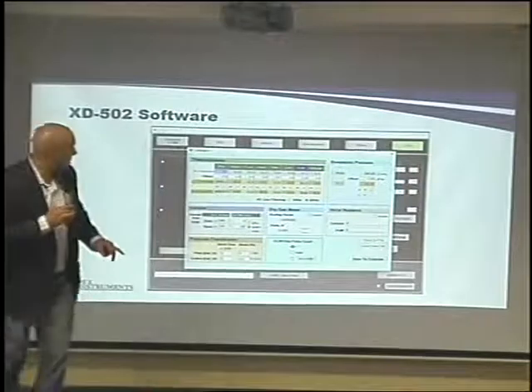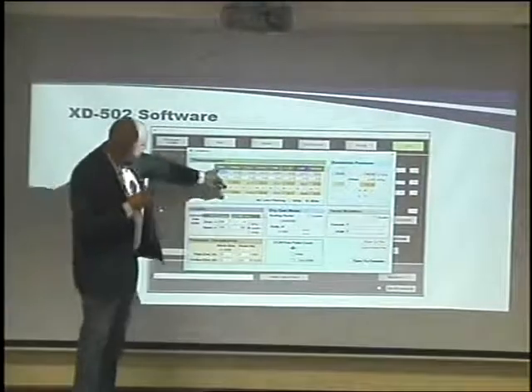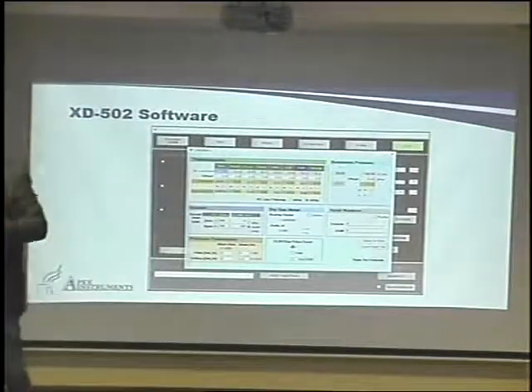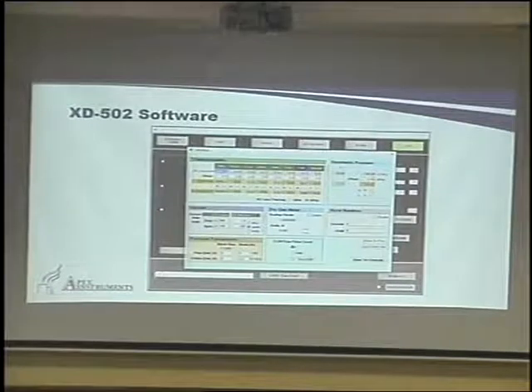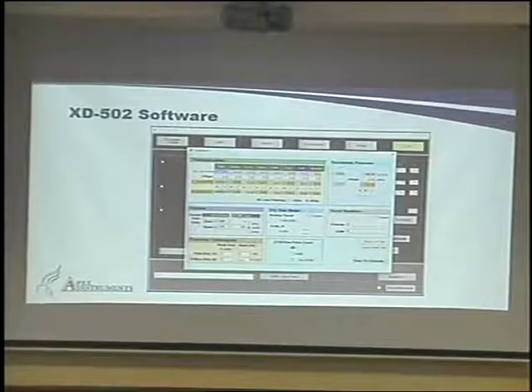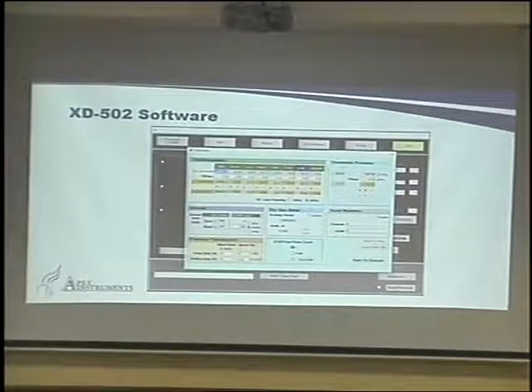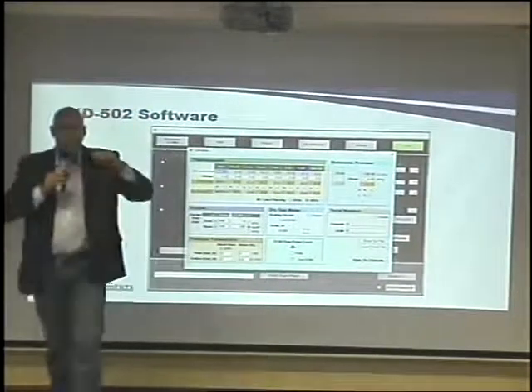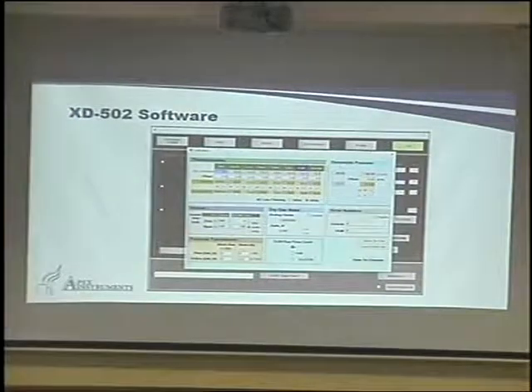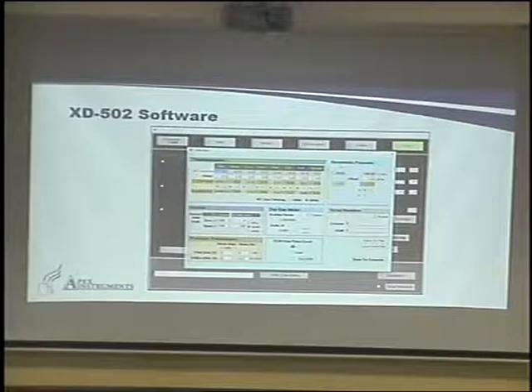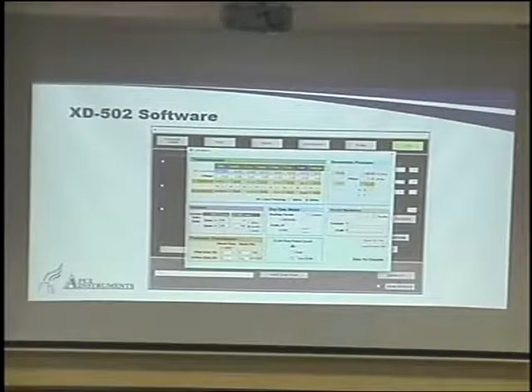It's not super clear there, but you can see, for example, this says our auxiliary TC, AUX. We can plug in a thermocouple simulator, or we can put it in an ice bath with a thermometer. And if we have a discrepancy in the reading, it's as simple as hitting a plus or minus button to get those two values to match. Then we can save it, and we've set an offset on the TC, and now that thermocouple is accurate and ready to be used again. So managing the equipment is actually quite simple as well with the software.